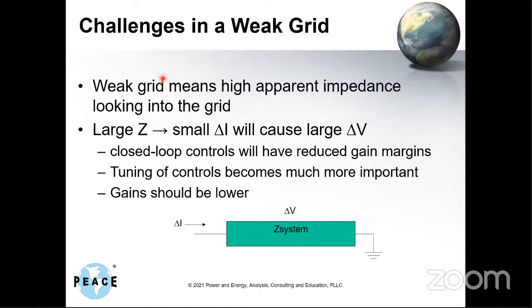Now, what are the challenges with weaker grids? As your system gets weaker, and let me quantify that, as the short circuit strength... so synchronous machines naturally give you short circuit current, right? So when we have a fault, it just naturally gives us short circuit current. And there's no inherent current limiting device other than the internal impedance of the machine. So if, say, your subtransient reactance is 0.2 per unit, then you could get as much as 5 per unit current, right?